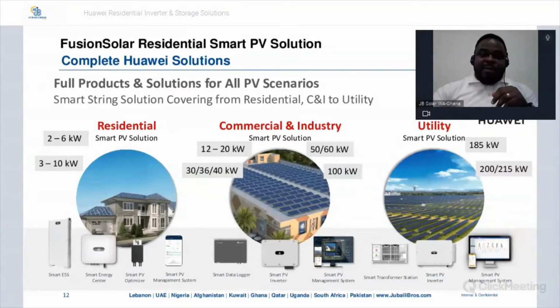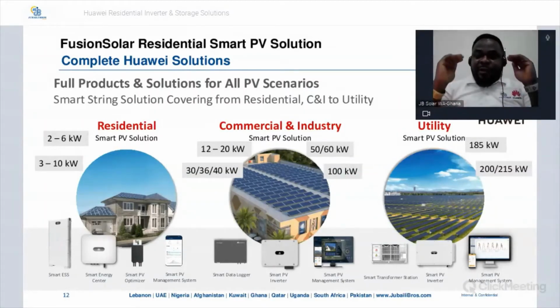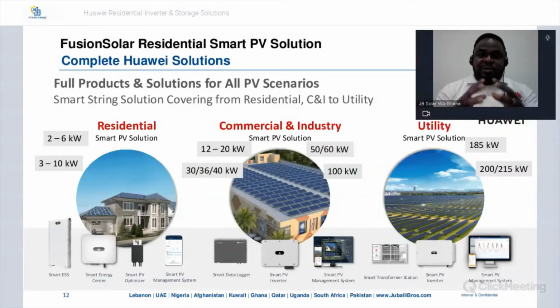And then the ultimate inverter, in my opinion, the 100 kilowatt inverter, the mega inverter. It has 10 independent MPPTs, and each MPPT has 2 strings. So in total, you can connect a maximum of 20 strings to this inverter directly without using any DC combiner box. Take note, Huawei inverters, because of their multiple MPPTs and string inputs, don't need a DC combiner box. This particularly saves you some capex, right? So you don't need a DC combiner box for the systems.